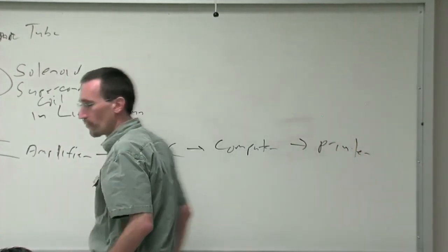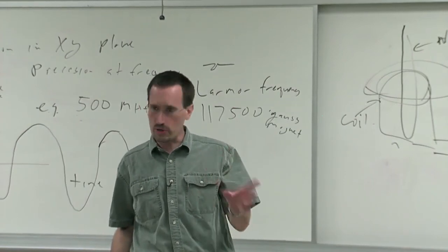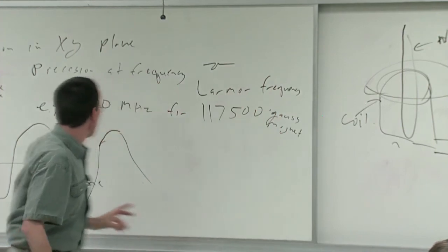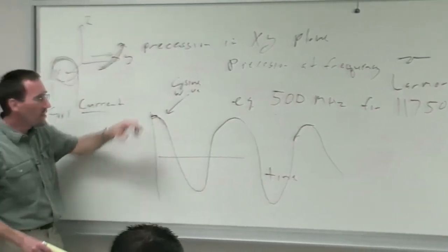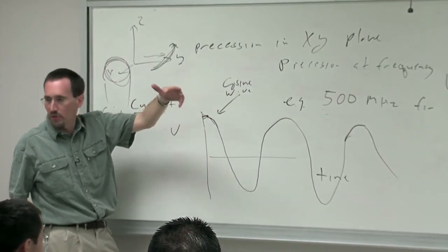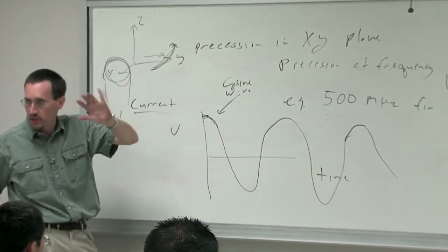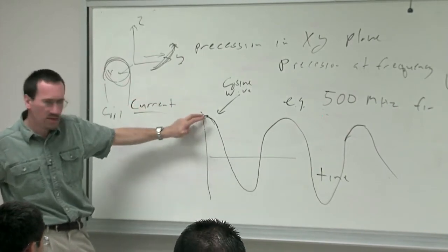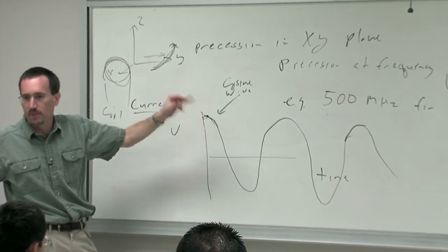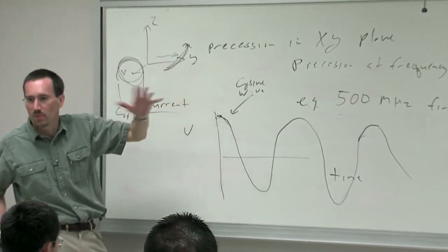And for those of you who've run an NMR spectrometer, you probably know the command RG, receiver gain. Who's heard that one? What you're doing there is basically saying, OK, we want to have as big a number as possible. If we had an 8-bit analog to digital converter, in other words, 8 digits of 0 or 1, you want your biggest signal to fill up that thing to be as close as possible to 1, 1, 1, 1, 1, 1, 1, whatever 8 ones is.